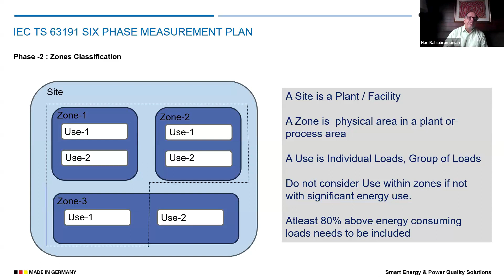So you have zone 1, zones, uses and site in the zone classification, which we need to understand. The same applies for the power metering and monitoring device and power quality device, PMD and PQI. This can be a combination of one or more devices with several functional modules. We call it a simple multifunction meter, but no one specifies what functions it performs. We only say it's a multifunction meter, but no one has clearly defined what the functional modules are. This is very important - we need to know what kind of measurement that particular meter is doing.